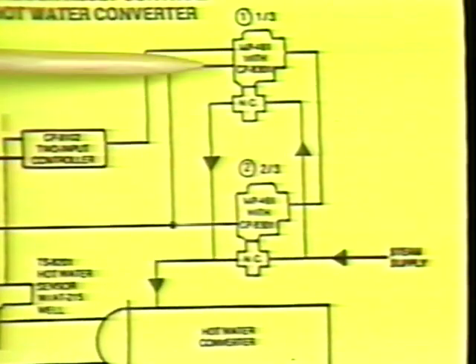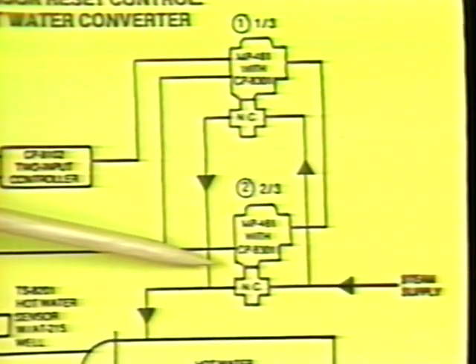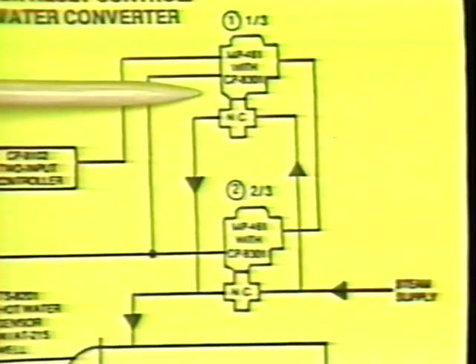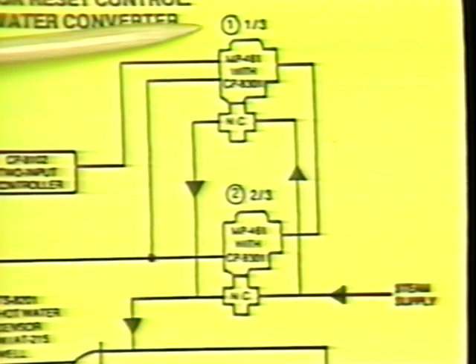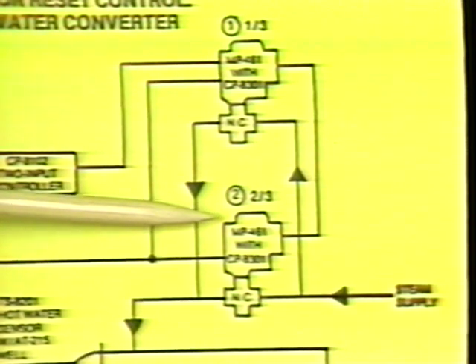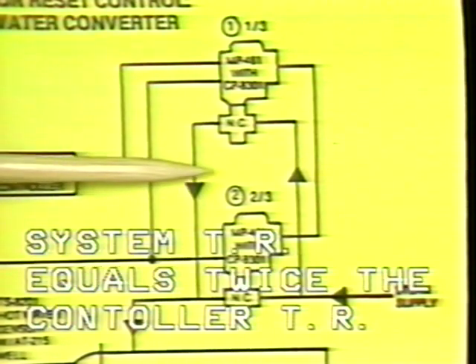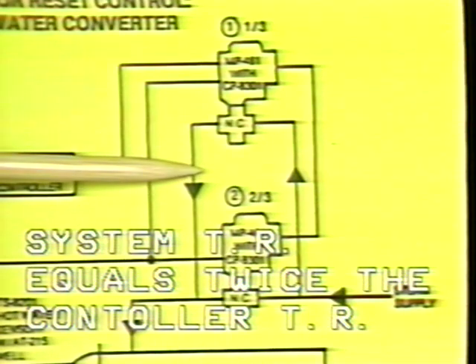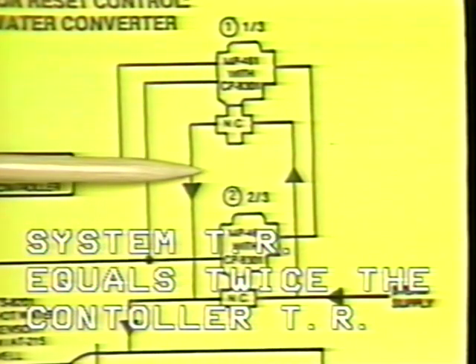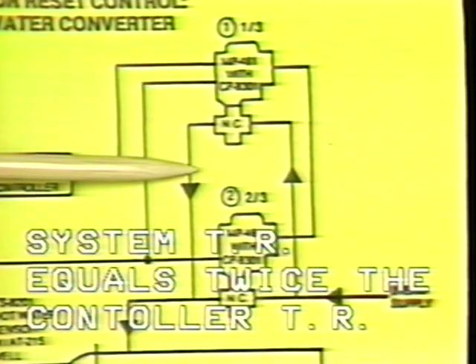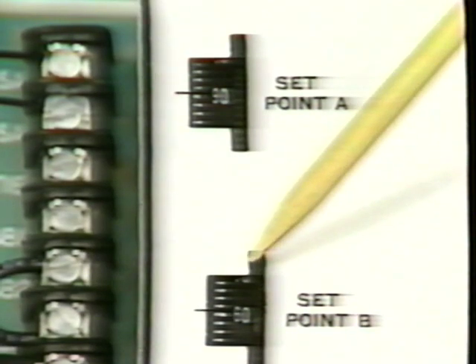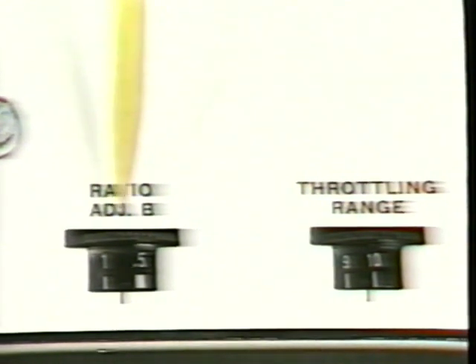In addition, we have 2 devices to control this time instead of 1. Each will require a 3-volt signal change for full response. 3 volts, 3 volts, a total voltage change of 6. That's 2 times whatever the controller throttling range is. In this example, the system throttling range will be twice the controller throttling range. Based on our example, set point A should be set at 90 degrees, set point B at 60 degrees. Our ratio was determined to be 0.67 as set here, and the controller throttling range 10 degrees.